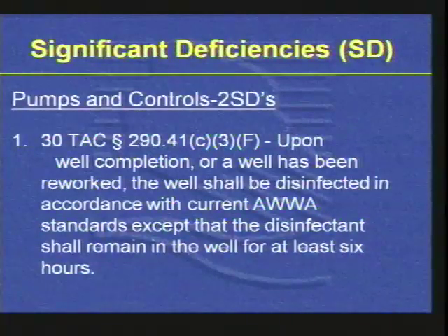Pumps and controls. We identified 2 significant deficiencies under this element. The citation is 29041C3F. Upon well completion or a well has been reworked, the well shall be disinfected in accordance with current AWWA standards, except that the disinfectant shall remain in the well for at least 6 hours.